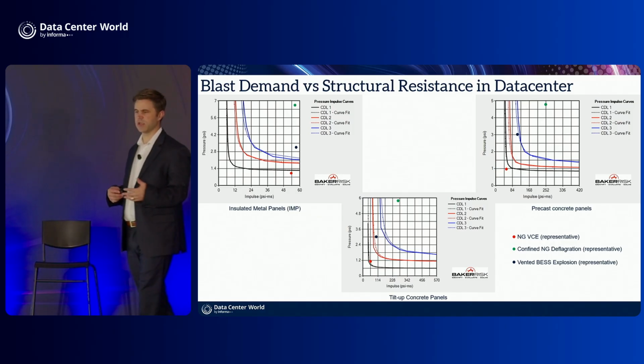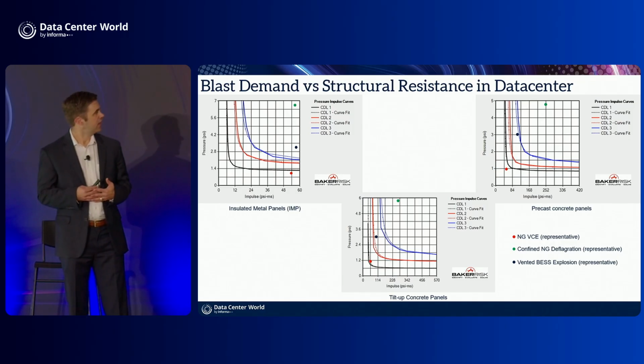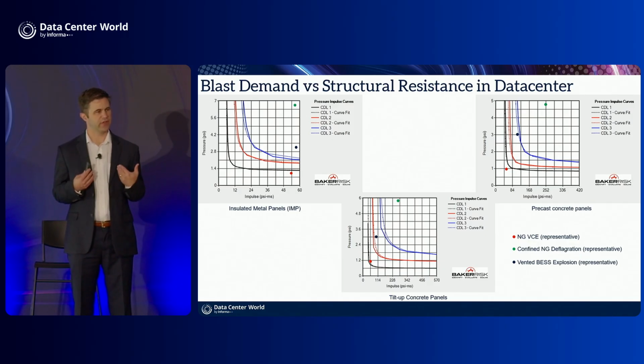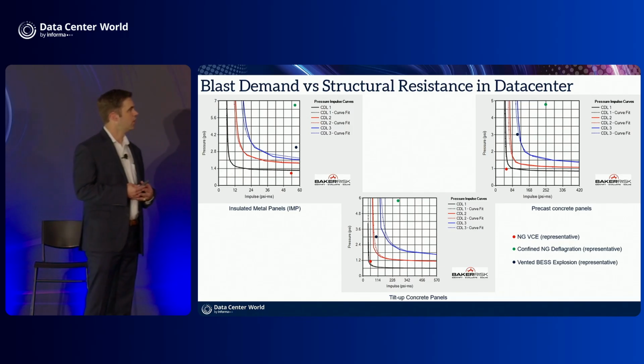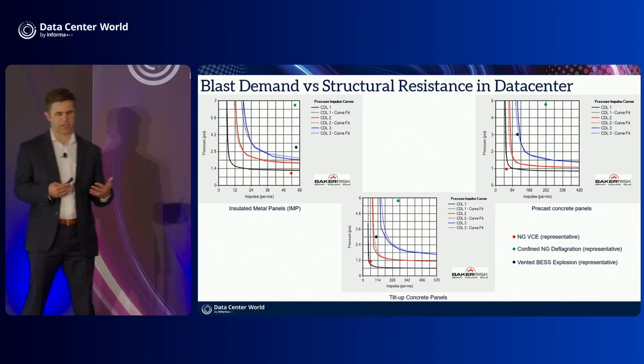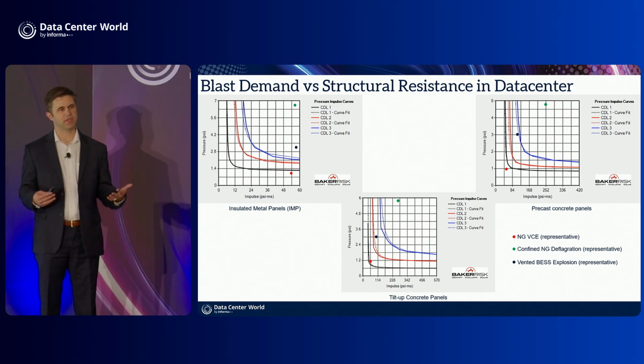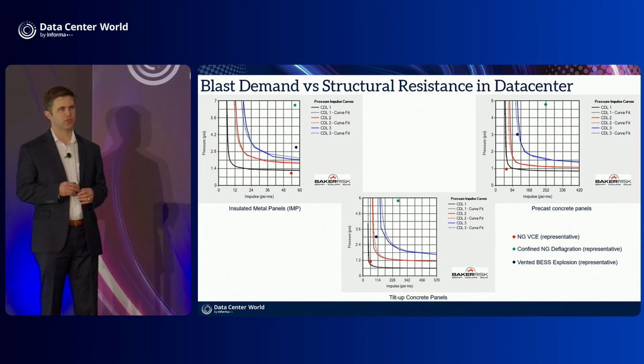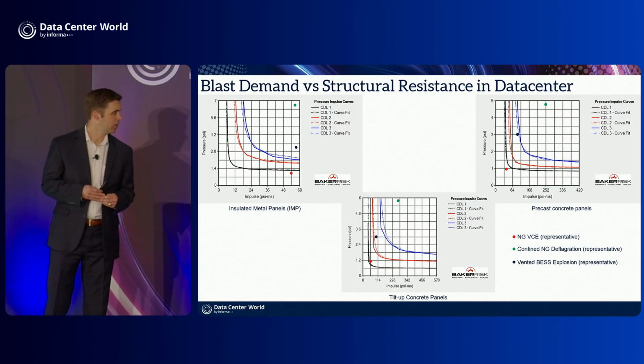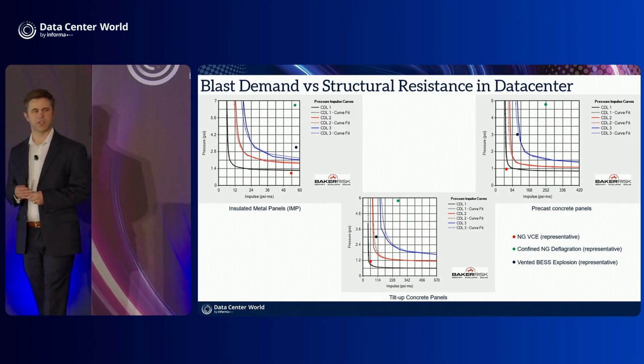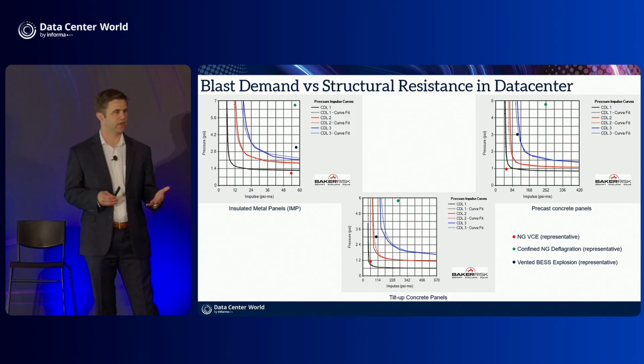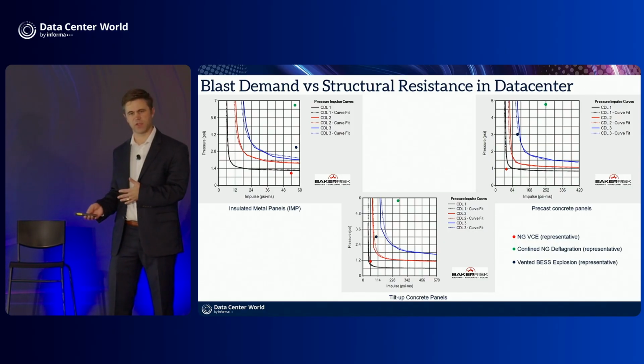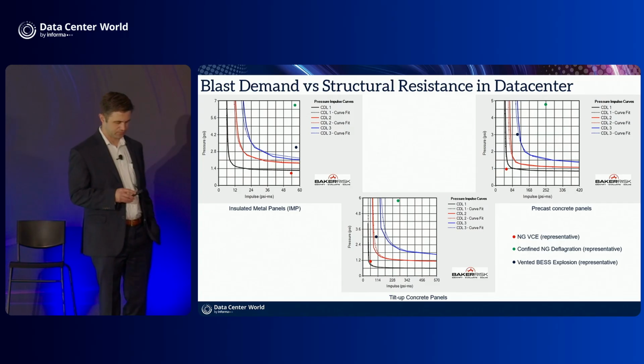What we demonstrate here is that if I take the loads produced from our test and apply them to those capacity curves I showed 4 or 5 slides ago, we see that for each of the cases we talked about, they have the potential to cause more than structural damage, but potentially structural failure to components typical at data centers, whether insulated metal panels, precast concrete, or tilt-up concrete. This possibility exists for events that have happened in industry, which we've replicated in test conditions.